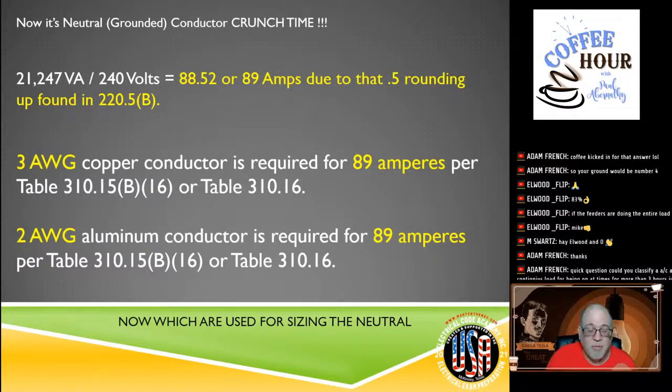Now, in our case, remember something. Since we got to adhere to 110.14(C) and we're under 100 amps, you typically would say, well, I'm going to have to go to the 60-degree column. All right, so I'm going to tell you that most times in these cable assemblies, what you're using is THHN, THWN-2, and the terminals are going to be rated 75 degrees C. So you're going to use the 75 degrees C value. Okay. On an exam, just be careful in your calculation and make sure you validate all of that information. Okay. But I'm going to tell you right now that we're using THHN, THWN-2 for our application. So I'm just giving you that information.